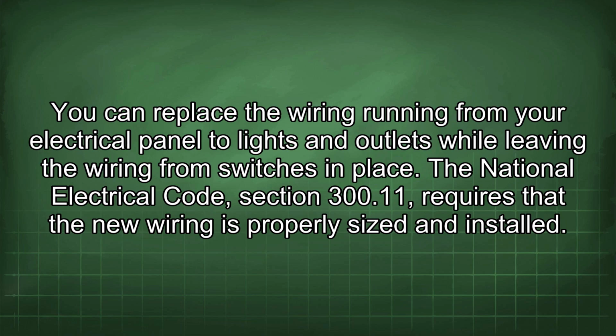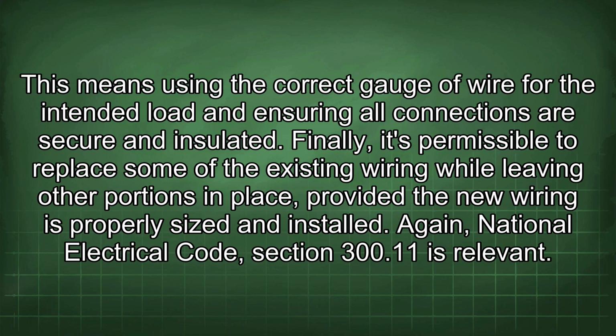You can replace the wiring running from your electrical panel to lights and outlets while leaving the wiring from switches in place. The National Electrical Code, Section 300.11, requires that the new wiring is properly sized and installed. This means using the correct gauge of wire for the intended load and ensuring all connections are secure and insulated.